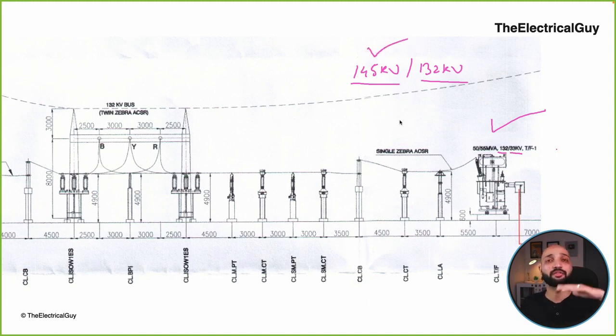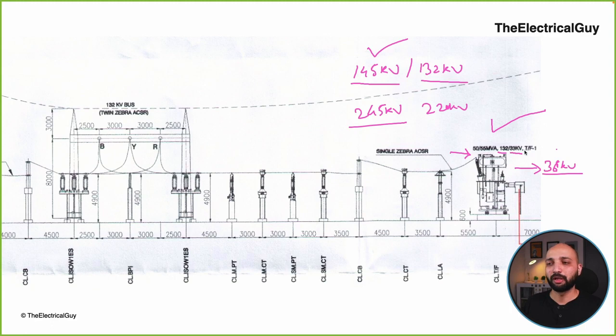So all the equipment that you will see here in the substation are rated for 145 kV voltage level. That is part of standardization, and it is always a good practice to refer to a voltage rating with its rated voltage. So instead of saying 220 kV, you should say 245 kV. That is a good practice. Instead of saying 400 kV, we should say 420 kV, right? That is the difference. So what this transformer is doing, it is accepting 145 kV as the primary input, and at the secondary it is giving 36 kV as the output. So this is a step down transformer. Now if the situation is vice versa, primary is 33 kV and output is, let's say, 145 kV, then it is called as step up transformer.